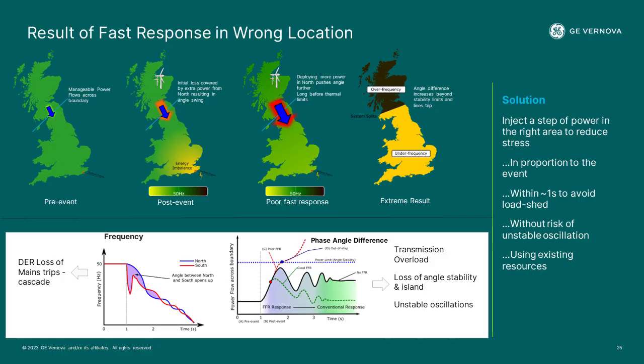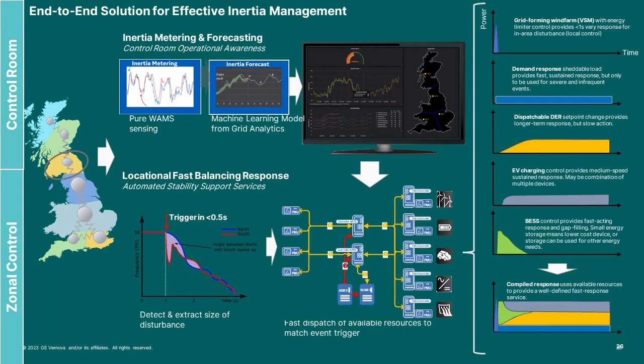And so with our WAMS solution, we have something called fast locational balancing, which can use the fast resources such as batteries, etc., but also use them at the right location such that you're restoring frequency while ensuring that you're not adding additive stress to the grid. You're maintaining the stability of the grid. And so with our effective inertia solution and with our locational fast balancing solution, we've got an end-to-end offering for managing low inertia grids with higher penetration of renewables.